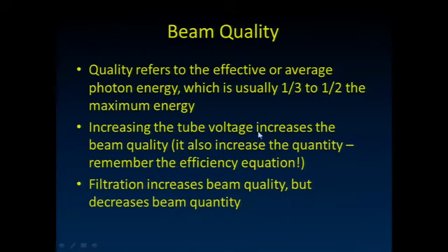Okay? We talked about increasing the voltage increases beam quality, but if you increase voltage, you also increase the quantity of X-rays that were produced. Remember our efficiency equation? Our kV times our Z times 10 to the minus 6.